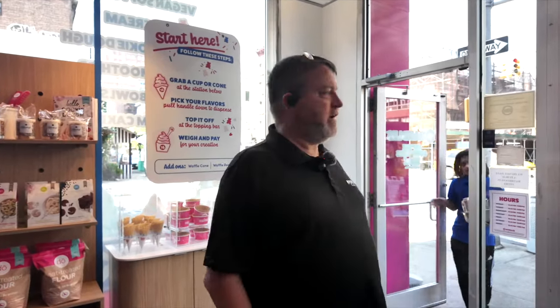We're going to be heading out from the customer site. Danny and Tommy are still working on the units — they found that there's at least one bad compressor. We're going to have to talk to the manufacturer about the handle issue, because the handles are being pulled too hard. That's because the customer comes in and does their own ice cream with those handles, so we'll talk to the manufacturer and see what we can do about that for the customer.